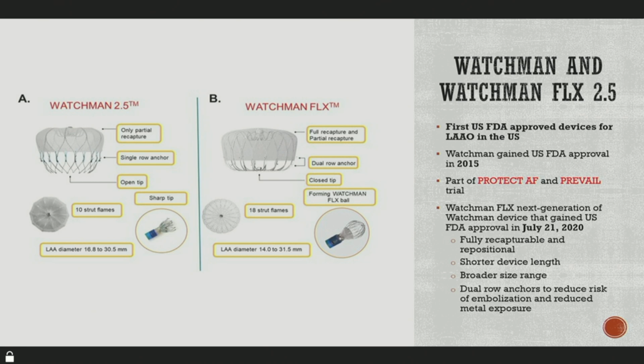The differences between the two devices can be seen visually here. The Watchman 2.5 device only allows for partial recapture, while the Watchman Flex allows for full recapture and partial recapture. That involves retracting the device partially into the access sheath or fully into the access sheath. As you can see, the Watchman 2.5 has a single row anchor, whereas the Watchman Flex has a dual row anchor. As far as the tip, the Watchman 2.5 is open versus the Flex, which is closed. And there are more strut frames as far as the Watchman Flex goes. And then the Watchman Flex can encompass a broader size range of the left atrial appendage orifice.